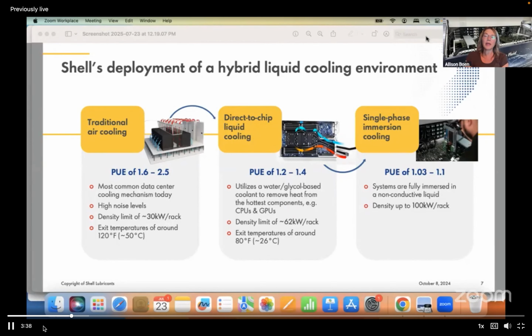You got to visit us last week for our lunch and learn at the Shell Data Hall in Katy, Texas. That's a 7 megawatt data hall. They were effectively out of power and could not expand any further. So the hybrid environment Shell has—with traditional air, they were hovering between 1.6 and 2.5 PUE.